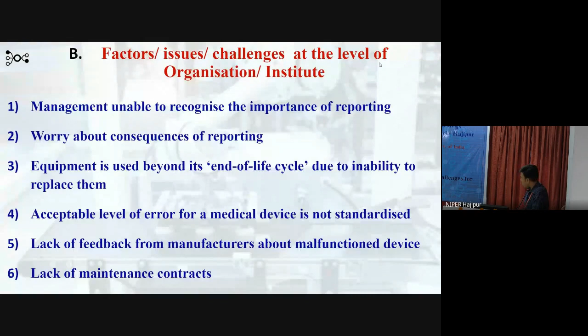Also, some of the equipment is used beyond its end of life cycle due to inability to replace it. As Dr. Satyendra Shukla has delivered, refurbished instruments are used. Refurbished instruments may be taken from a good manufacturer, but some of the hospitals are using instruments beyond their end of life cycle. Also, they are not standardizing the acceptable level of error. For any medical device, they have to standardize the acceptable level of error. Also, there is lack of feedback from manufacturers about malfunctioning devices, and lack of maintenance contracts can also result in adverse events.